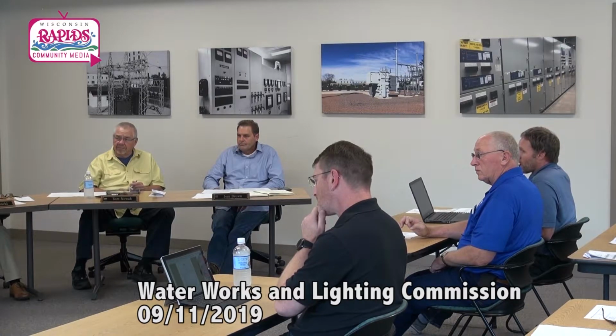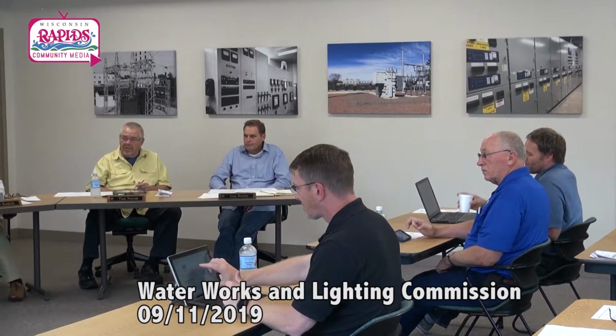Hey Todd, don't you usually, when you have test equipment or very finicky equipment, use constant voltage transformers or something? They could do a number of things on their side too. A lot of times you have isolation transformers where it's basically the same voltage going in and out, but it actually makes the voltage more constant.